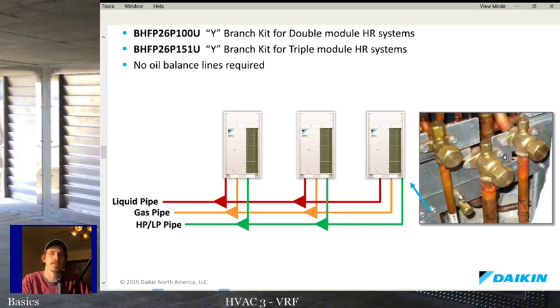Same thing with ducted VRF systems. A lot of them have a really low static pressure that they can maintain coming out of the ductwork. You need to know what the minimum length for the line set is. There's mini splits where the minimum length is 6 feet. There's mini splits where the minimum length of the line set is 15 or 20 feet. And if you go under that, you risk compressor damage. So manufacturer's instructions are critical.